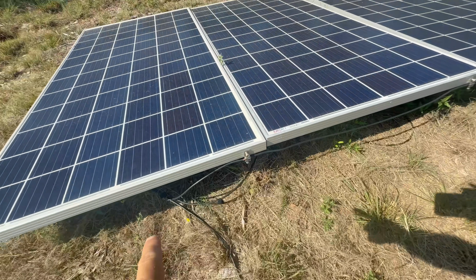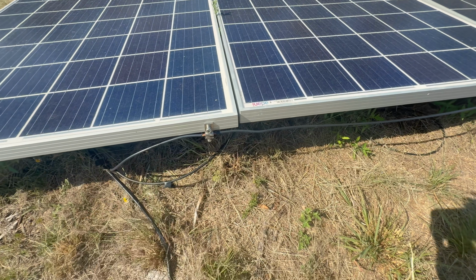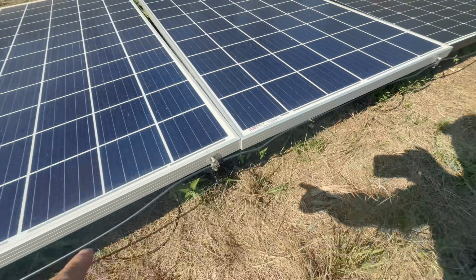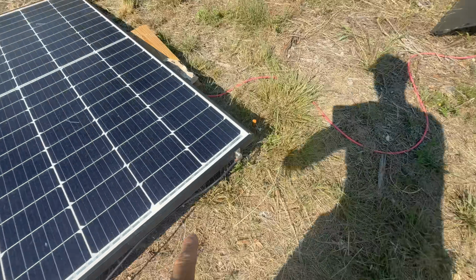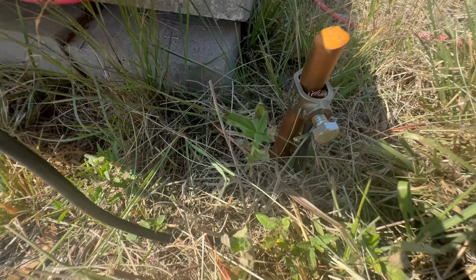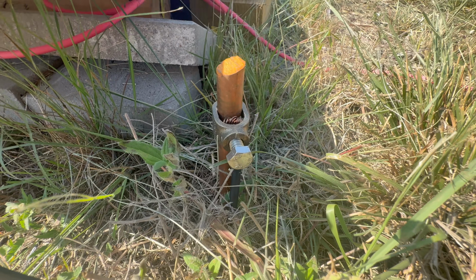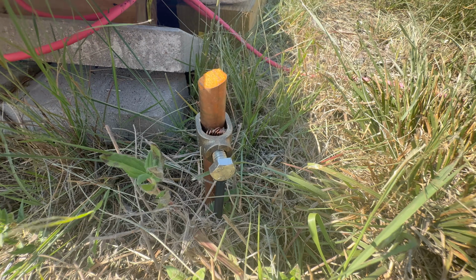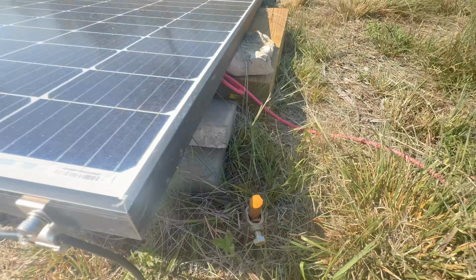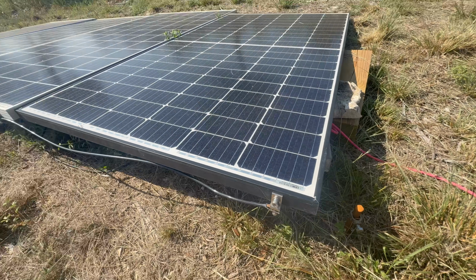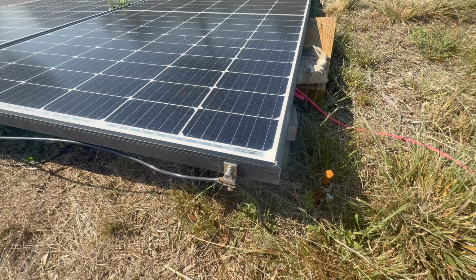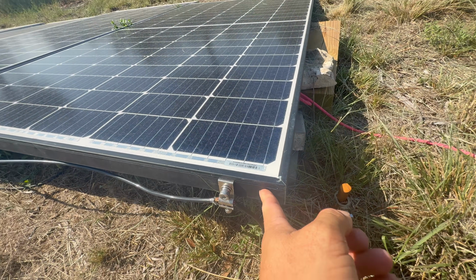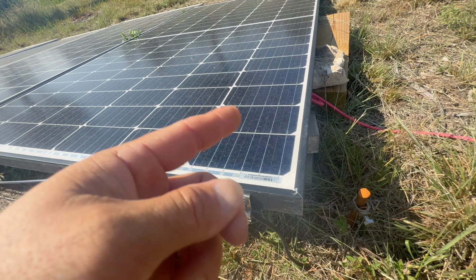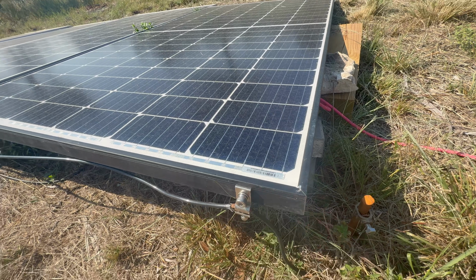And then the rest of them are wired, also grounded together all the way across each panel. I drove in a ground rod right here since the Jackery unit doesn't have a grounding port, so I put that in the ground just to be safe. Now they'll run without a ground wire, but if a wire gets frayed and touches the side of the solar panel, you could energize these panels, and then you become the ground and get shocked.